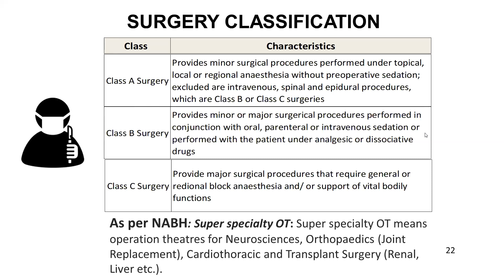So we are talking of the excerpts from what is required as per NABH in terms of temperature, RH, outdoor air, and recirculation air and pressure requirements. This is an excerpt from NABH. For super specialty operation theaters, the operation, as I said, is for neurosciences, etc. The temperature has to be 21 plus minus 3, and RH is to be 20 to 60%. Pressure has to be positive, and outside air, they expect you to have 4 air changes per hour, and recirculation is minimum 20 air changes per hour.